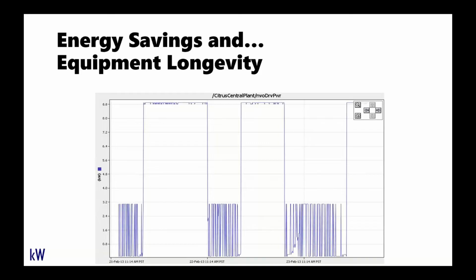So here's a graph of Citrus College's primary chilled water pumps. This was a graph that we collected prior to our first retro commissioning project. And what you can see here is the pumps are operating during the day when the chiller plant is on at about 8.8 kW up at the top. That's that nice flat solid line at the top. But then when the system is off at night, the chillers are off, and actually what we saw in the data was that the pumps, which should have also been off, were cycling rapidly. And this is obviously causing excess energy consumption because the pumps are turning off, on, and running.